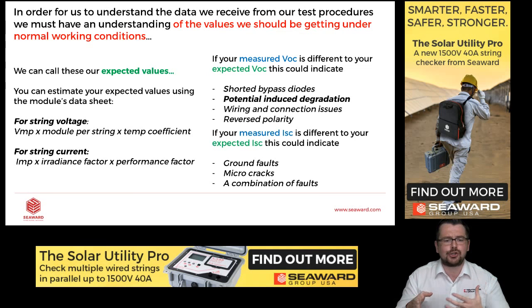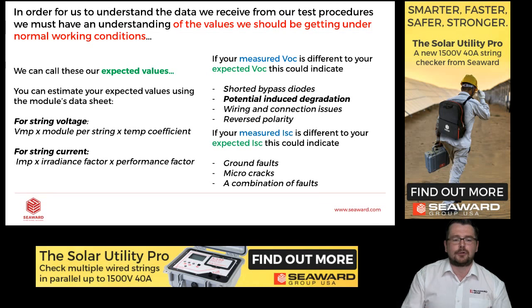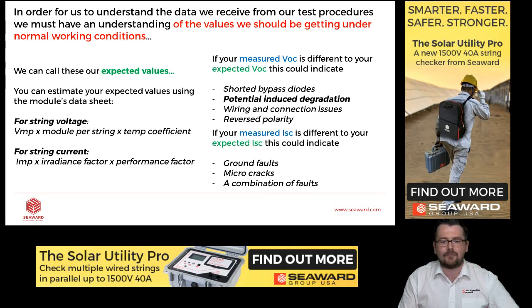Similarly, if your measured short circuit current is not in line with your expected short circuit current, this could mean we have ground faults, or the most popular one, or the most unpopular, but most prevalent I find, is micro cracks. And these are hairline cracks in the PV cells which cause shunt resistance. That energy has to go somewhere, it's released as heat, so you can also diagnose these with an IR camera. Or generally, if your ISC is low, it could be a combination of faults also. So don't think we're only going to have one fault on a PV array.